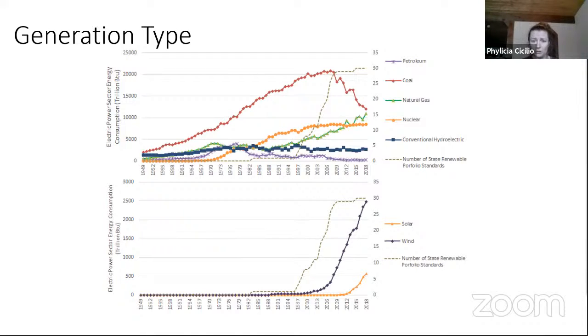Now, solar and wind, seen on the bottom plot, do not have rotating machines that directly physically connect to the grid like large synchronous generators. They don't have inertia. Now, I say that with the caveat that they can use controls to have inertia-like responses if paired with storage, or the generator has to operate at lower than the maximum power output. But the key takeaway is that they don't have rotating machines that create this inertia. So existing control systems that act to stabilize the system after faults are designed to work with synchronous generators that act on this longer timescale than inertialess solar and wind. Therefore, as your system adds more and more solar, wind, and/or storage, there has to be an adjustment to control and protection systems to account for their different, faster dynamic behavior.